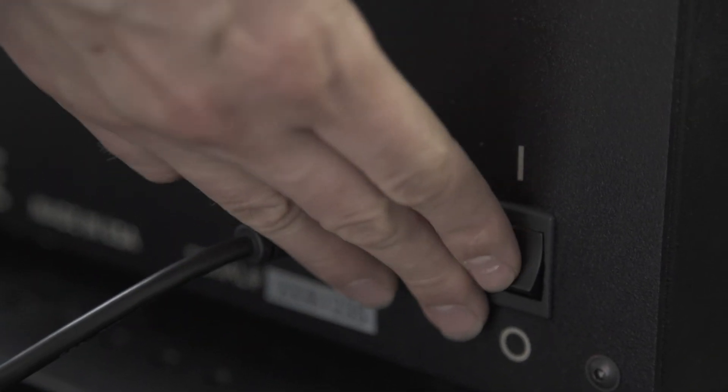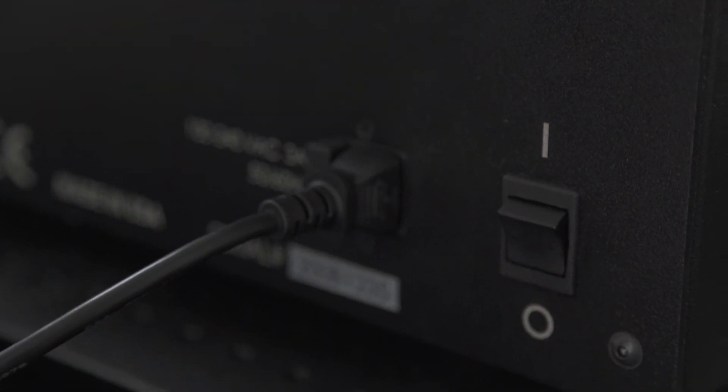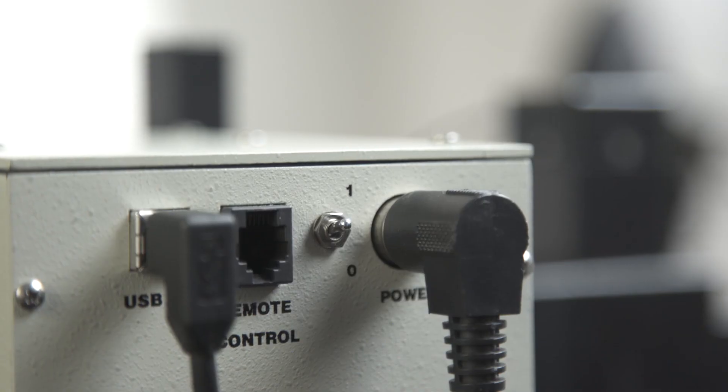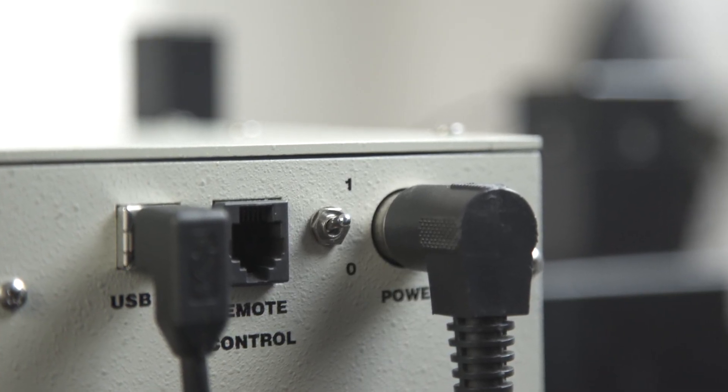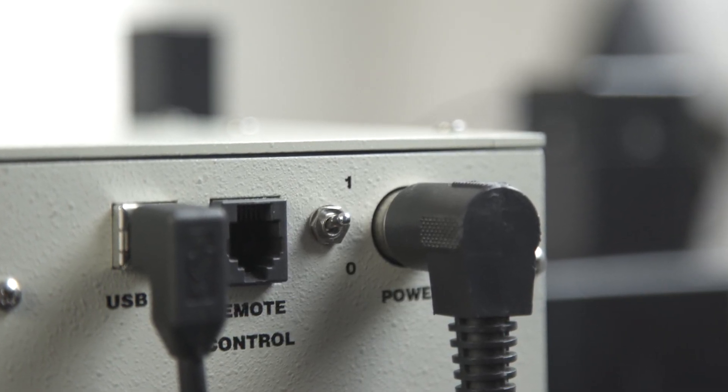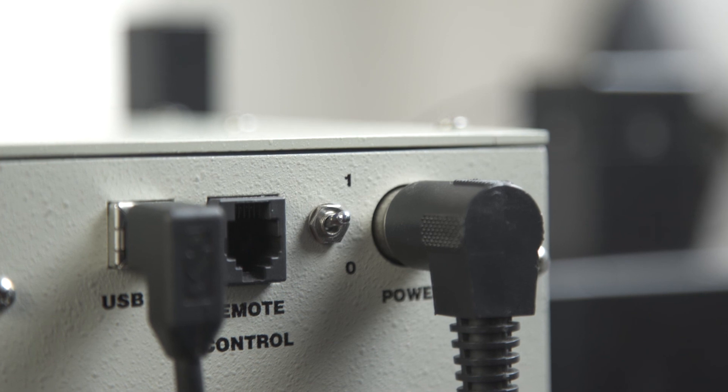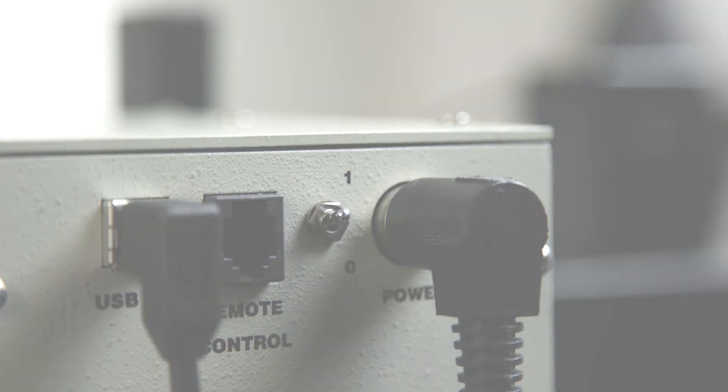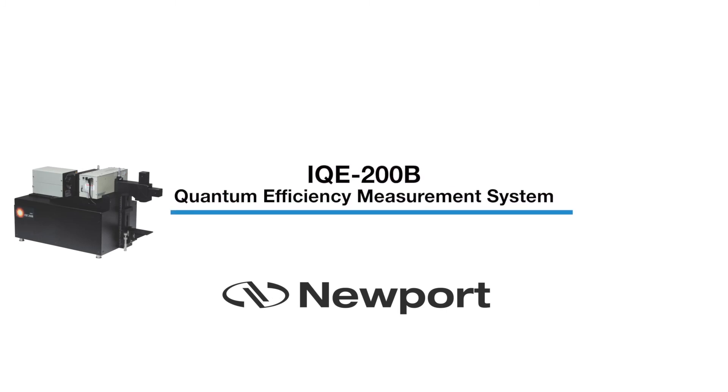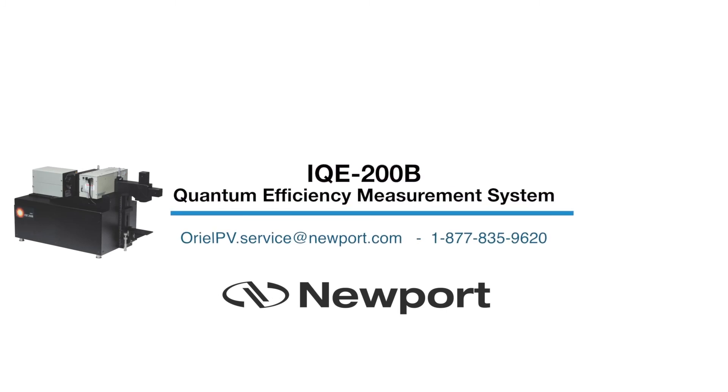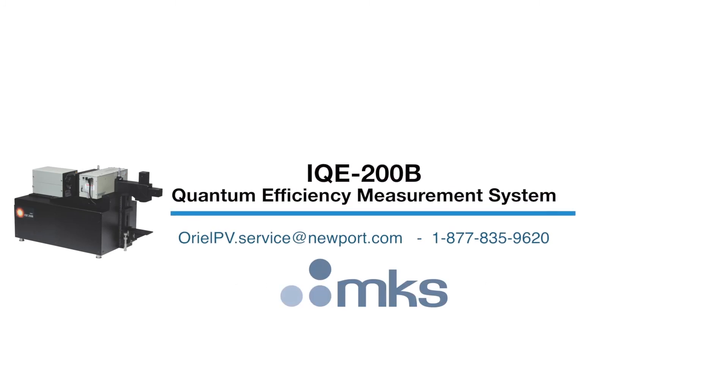Finally, we can power down the instrument from the switch on the rear panel. We may leave the monochromator switch in the on position, ensuring this component is always initialized at startup. As shown in this demonstration, getting a Newport Quantum Efficiency Measurement System safely up and running is a straightforward process. But if you have any questions, feel free to contact us directly at orielpv.service at newport.com or by calling the toll-free sales number 1-877-835-9620.